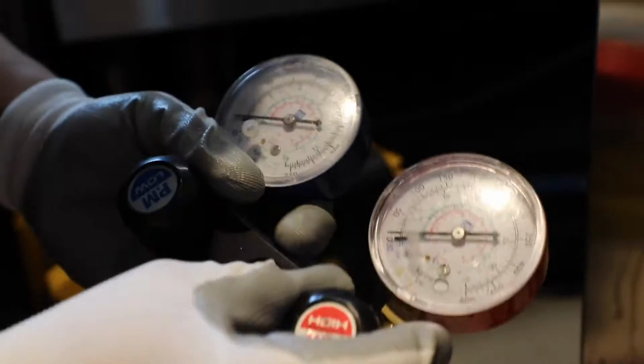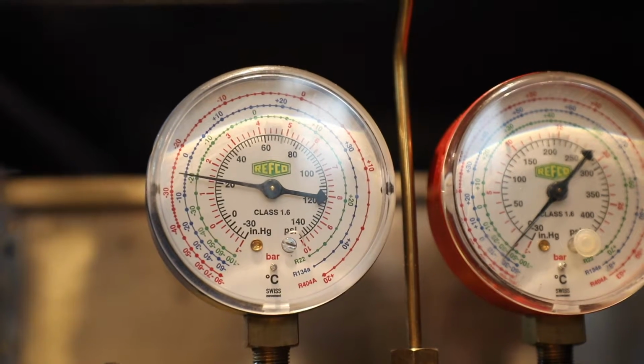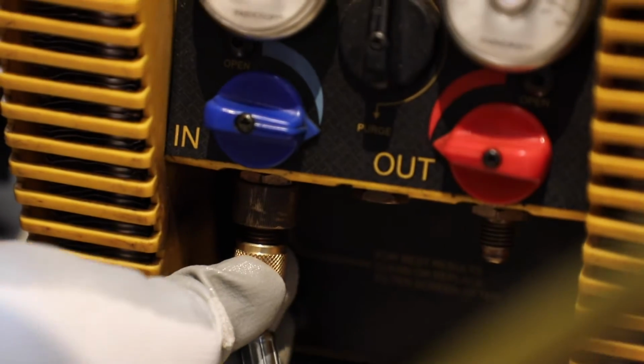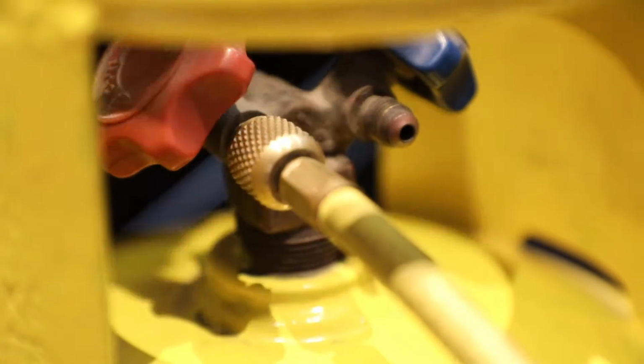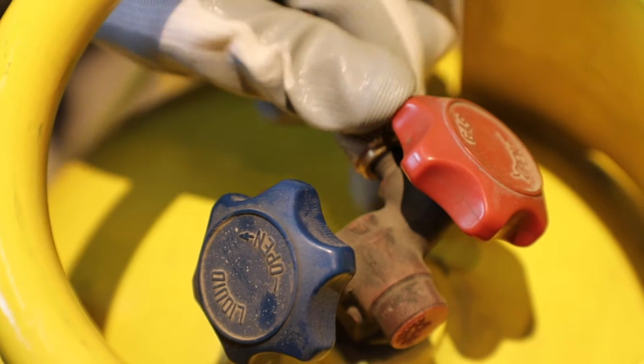And the process would be that the technician comes to start at the call out, so the unit's running high, he does his fault finding and he finds the unit's low on gas and there's a leak. He would come to repair it, he'd attach his gauges, they would recover the refrigerant out of it, they would then pump nitrogen through the unit so they can test the pressure, they would identify where the leaks are, and if they can repair it they would. We would then do the reverse process and top the fridge back up at the right pressure with the right refrigerant. And the difference being that we would keep F-gas records, so you'd know exactly what type and how much of this refrigerant came out, and exactly what type and how much of this refrigerant went back in.